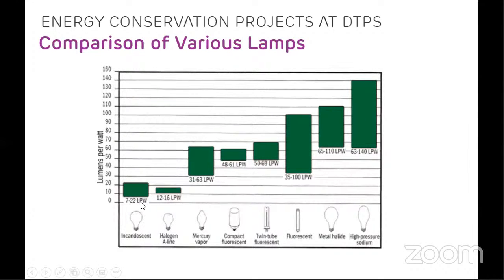Going to the next detail, you can see the rating of each lamp in lumens per watt. LPW is lumens per watt. Higher lumens per watt means better efficiency. High pressure sodium vapor lamps provide lumens per watt from 63 to 140. Metal halide lamps provide from 65 to 110. Fluorescent, which is our common tube lights, provide from 35 to 100. Now 35 to 100 lumens per watt means each watt of electricity consumed will provide 35 to 100 lumens, depending upon the type of the tube light or fluorescent lamp. Then twin tube or compact fluorescent lamp will provide 50 to 70 lumens per watt. Mercury vapor lamp will provide from 30 to 60 lumens per watt. So here you can see different types of lamps and their efficiencies.